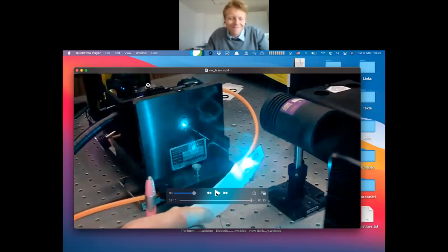The lens here has a cylindric shape because you want to have something like a lengthy focus point, not a point, but something extended in one direction, simply because this is the shape of your cuvette here, to reach or to excite a larger part of the dye that you are offering.